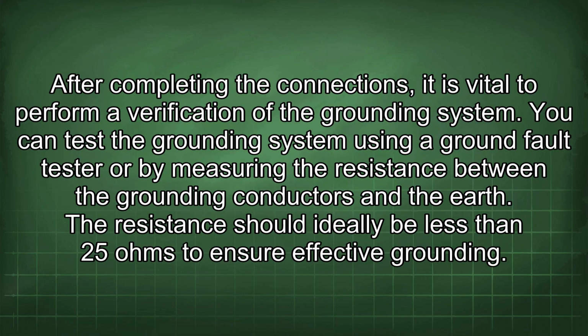After completing the connections, it is vital to perform a verification of the grounding system. You can test the grounding system using a ground fault tester or by measuring the resistance between the grounding conductors and the earth. The resistance should ideally be less than 25 ohms to ensure effective grounding.